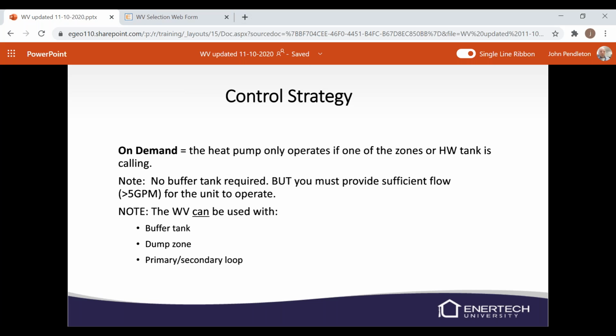Now we can use this with a buffer tank, and we'll cover that a little bit, or I should also say a hydraulic separator. You could also do a dump zone or a primary secondary loop. We won't cover those last two. I'll show you the buffer tank and the hydraulic separator here in a little bit and talk about those when we look at the piping, but we won't discuss the dump or the primary secondary loops.